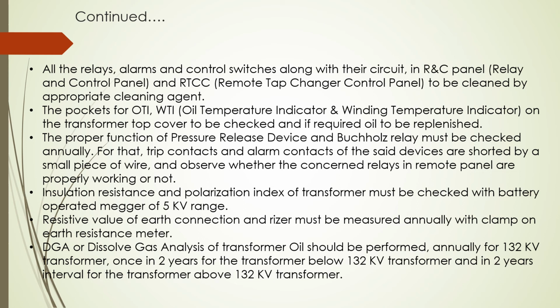DGA or dissolved gas analysis of transformer should be performed annually for 132 kV transformer, once in 2 years for transformer below 132 kV, and in 2 years interval for the transformer above 132 kV transformer.